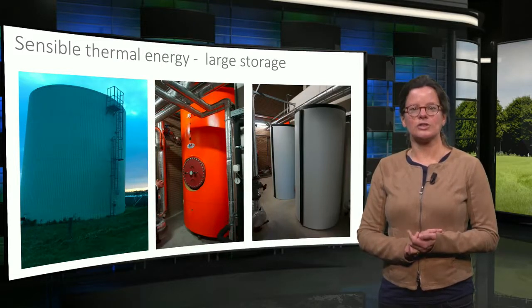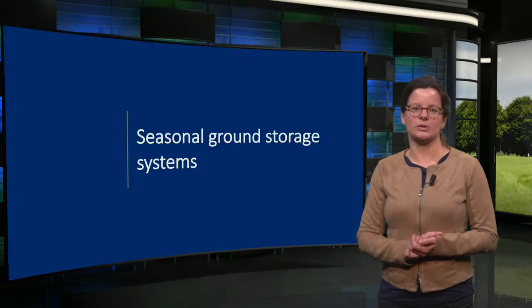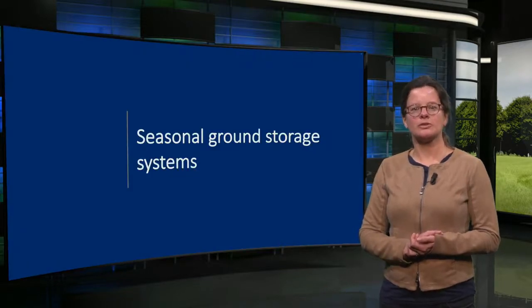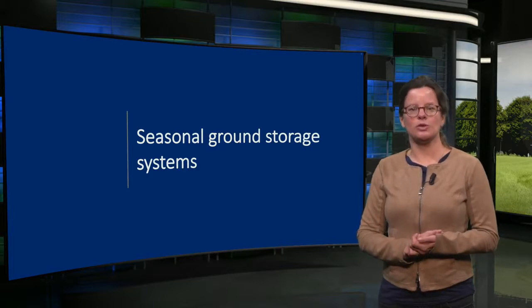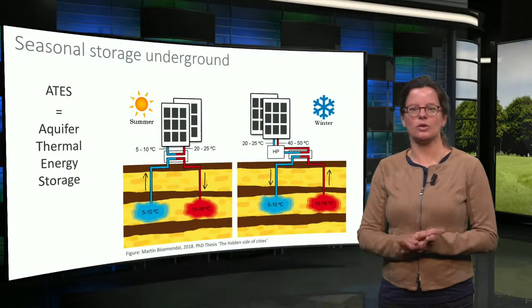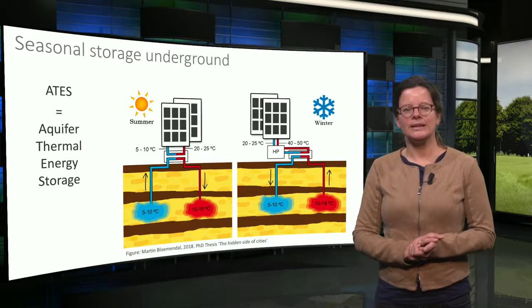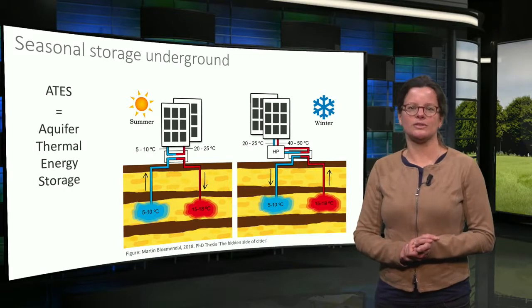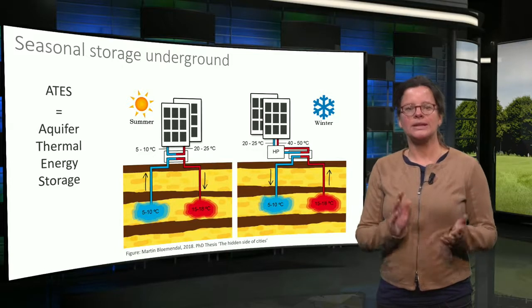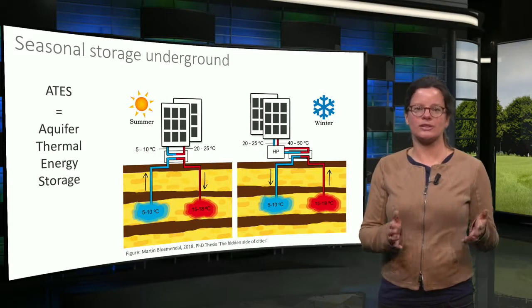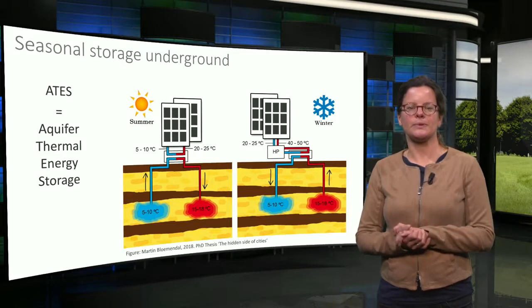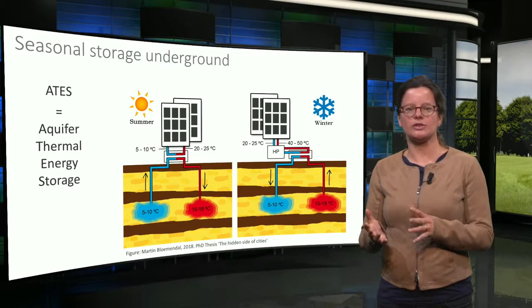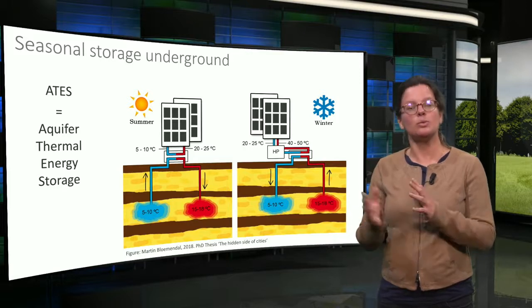Therefore, the subsurface is often used for seasonal thermal energy storage. Subsurface aquifers — underground layers of sand with groundwater — can be used to store heat. These systems are called ATES systems, aquifer thermal energy storage. In these systems two wells are drilled, which will become a cold well and a warm well. In summer, groundwater is extracted from the cold well. It passes through a heat exchanger in order to cool a building. The heat from the building is transferred to the groundwater, which is then injected into the warm well.